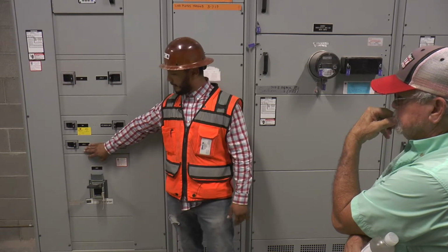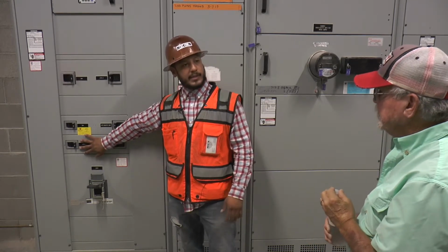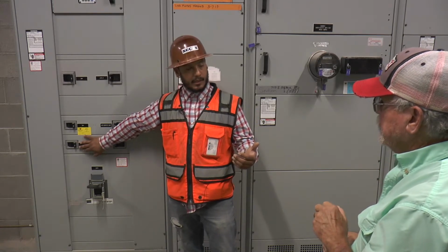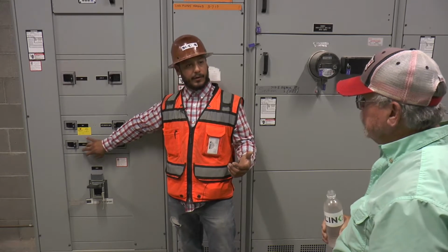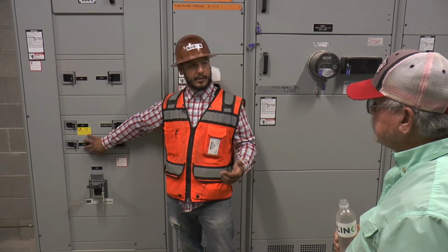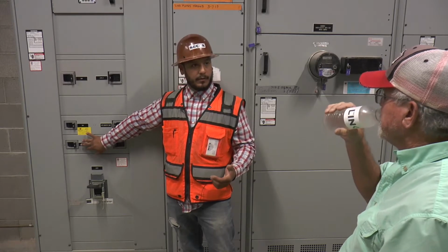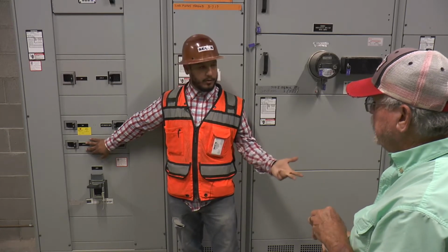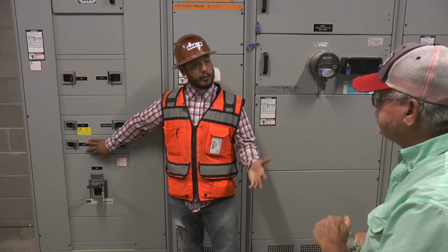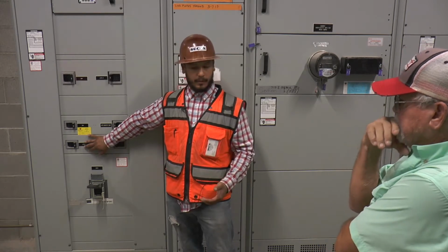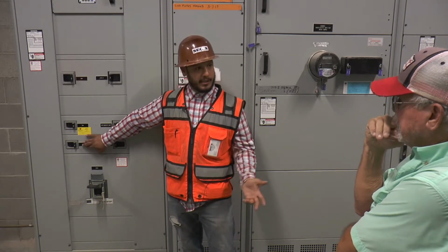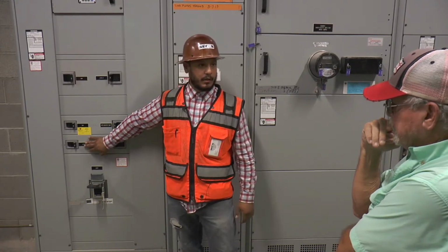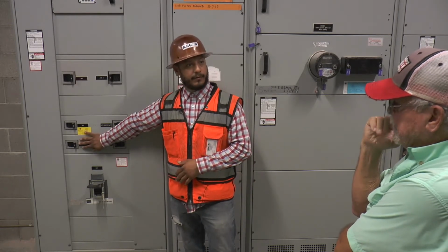This ATS1 here is also 480, but it's stepping down for all your common areas, which will feed levels 6, 12, 21, and 30, which are all EM panels, and they're stepping down from a transformer to 120 for your emergency lighting, exit signs, also door mags, fire alarm panels, booster panels that are on the upper floors. That's basically what this controls: egress, path of egress, all your garage lighting, and all the back of house will be lit as well. Any PC equipment also gets lit off of this too.